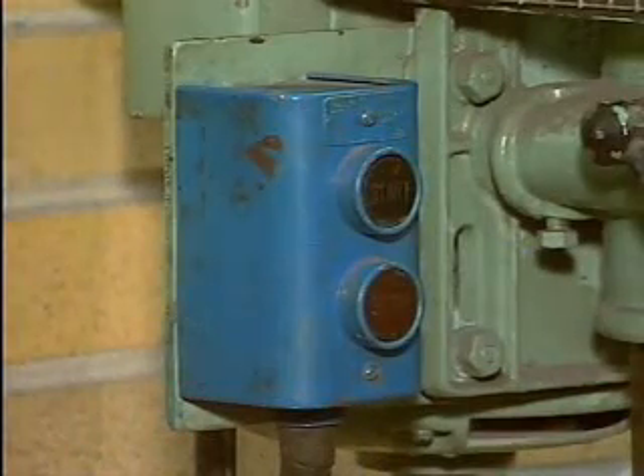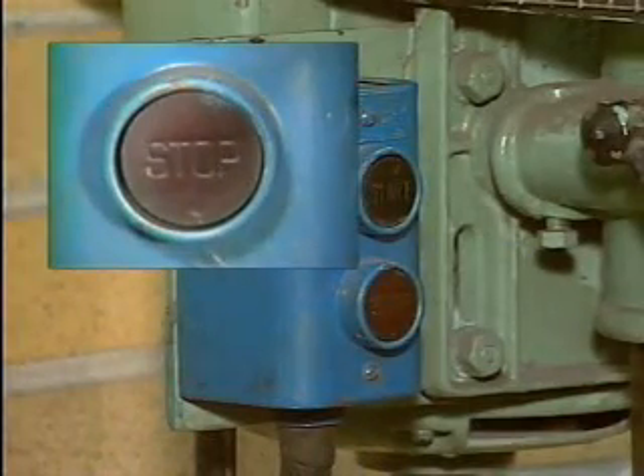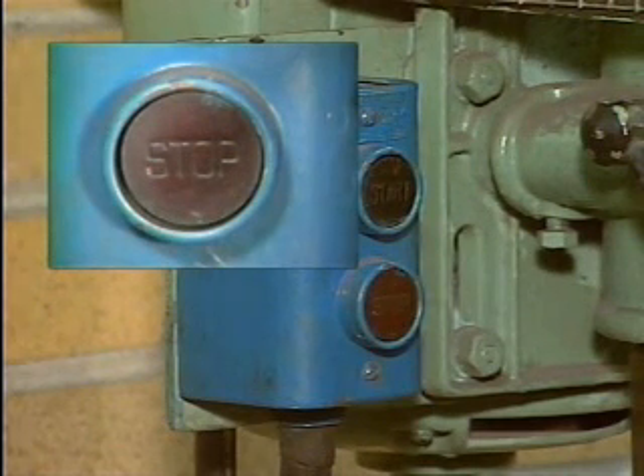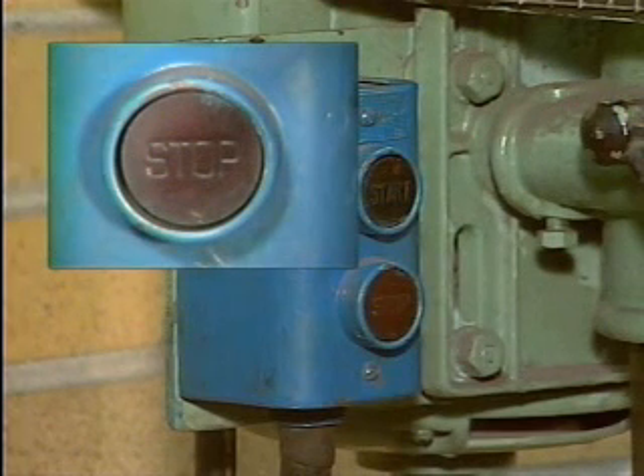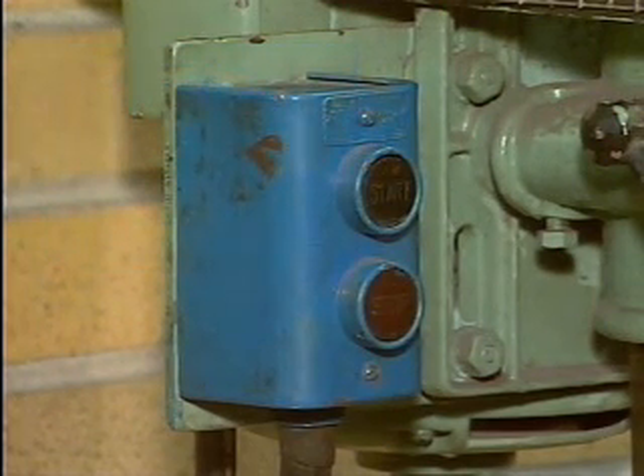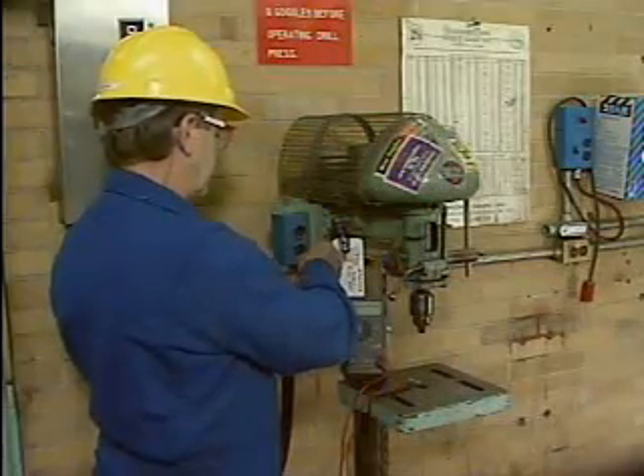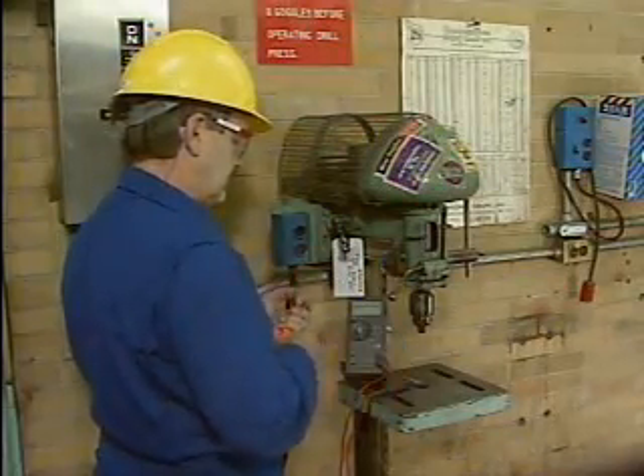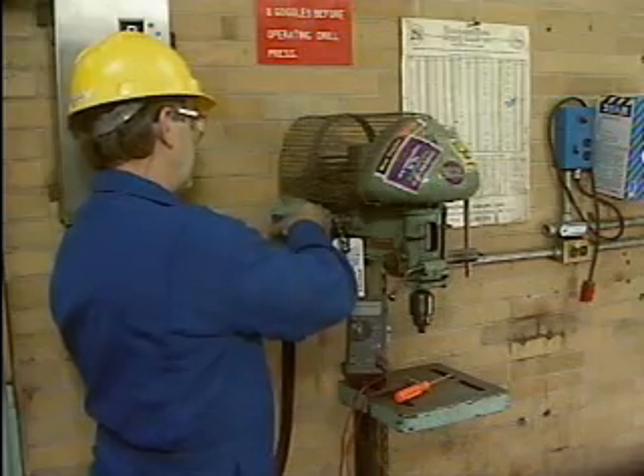The electrician thinks that the stop switch is more likely to have failed than the start switch. That's because, as a normally closed switch, it has current flowing through it more often than the normally open start switch. So he decides to check the stop switch first. After closing the control cabinet door, the electrician opens up the push-button station.